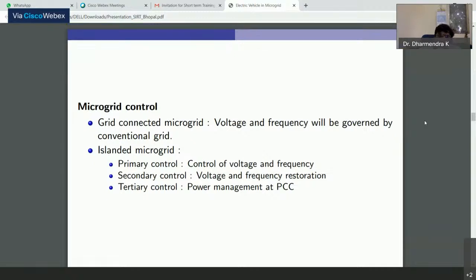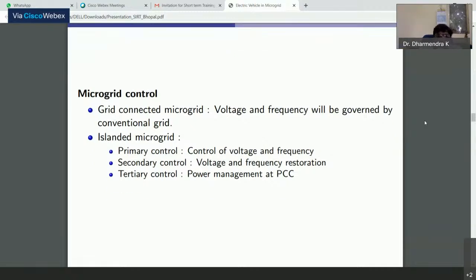Now, as I discussed about microgrid control: in grid connected microgrid, voltage and frequency are governed by the conventional grid. But in islanded microgrid, there are three types of control: primary control, secondary control, and tertiary control. The main difference between these is the action speed. Primary control acts instantaneously.